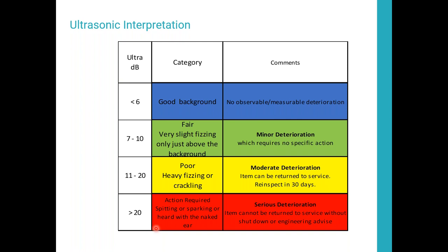One thing that cannot be determined by most PD test sets is, if I have a value of, say, 30 dB, how long before I fail? What's my time frame? It's not that easy because, yes, you have a lot of activity, it's strong activity, but you don't know how much insulation material you have left between where that activity is happening and the ground point. So that piece of barrier board that I showed earlier, that had a piece about the thickness of a pencil, that may have lasted a month.